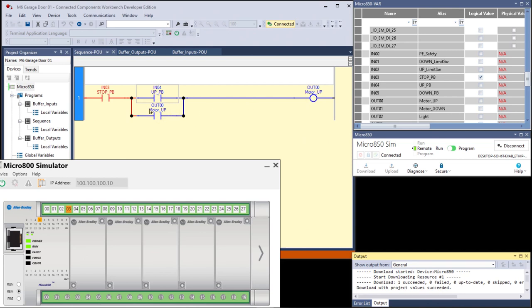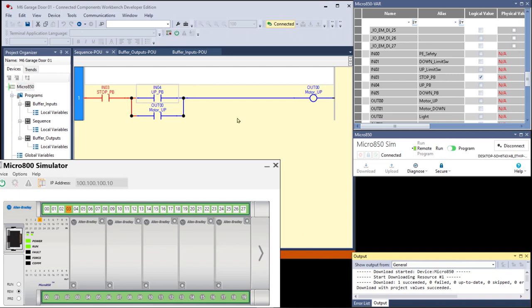This could be a relay coil and one of its relay contacts is used right here. So for the up push button, I'm going to turn that on. The whole rung goes true. Then I'm going to turn it right back off. So that's like pressing and releasing the up push button. So the motor runs until you go to input 3 and turn it off and then back on. Remember that all of our stop or safety devices are going to be wired fail safe, which means that they conduct electricity in the safe mode, the fail safe mode. That way if a wire gets broken, everything stops and you can't start it.